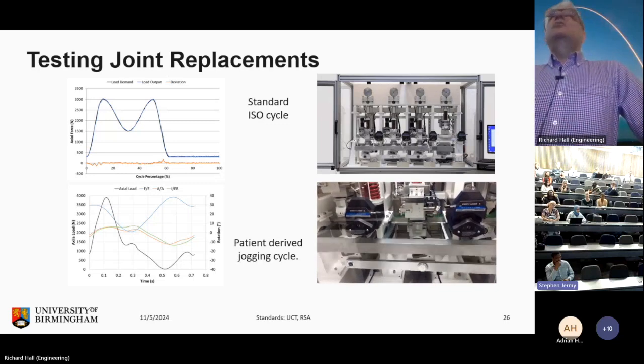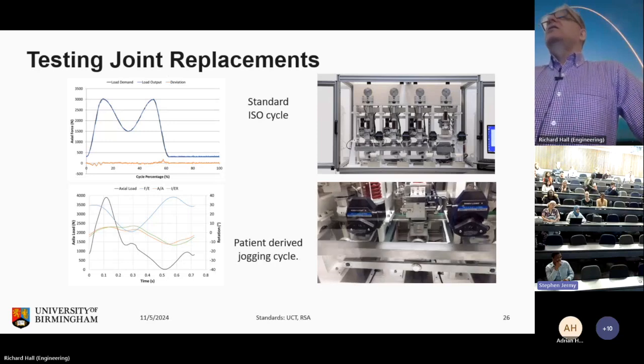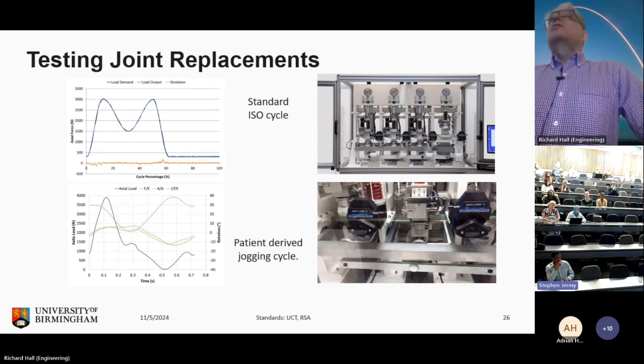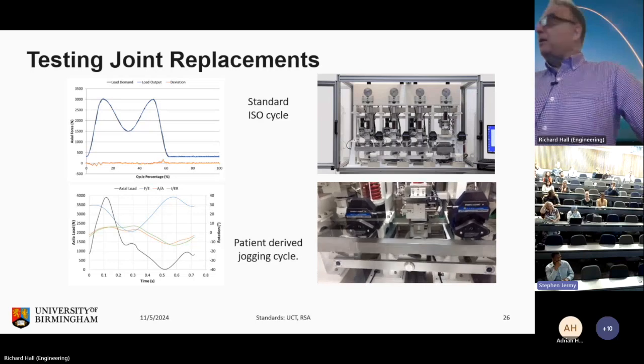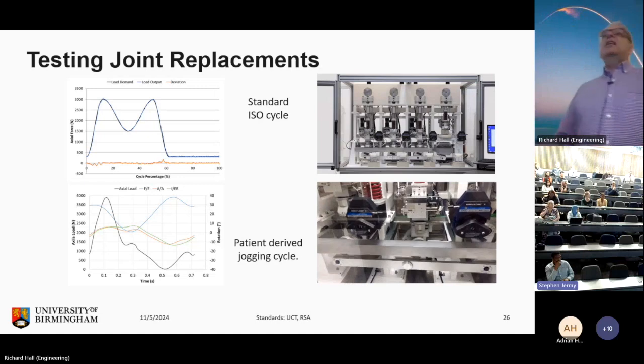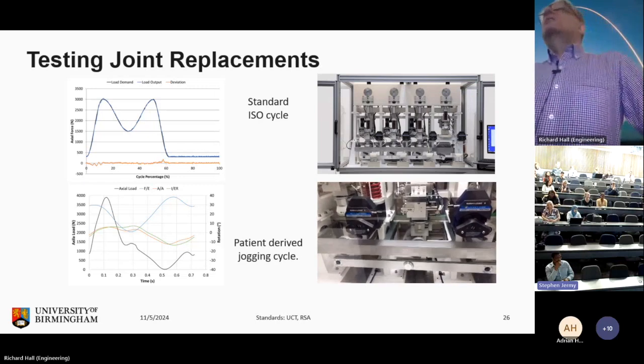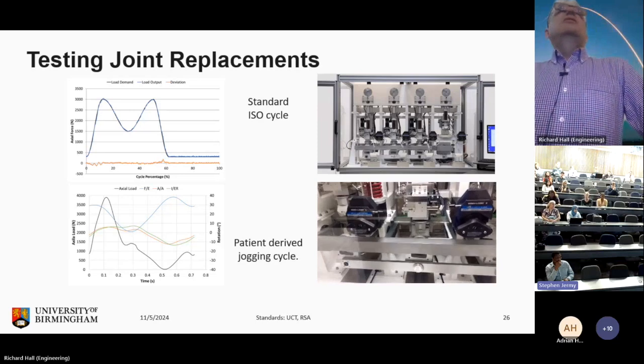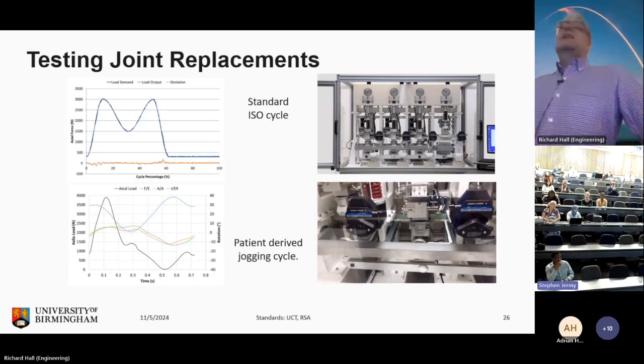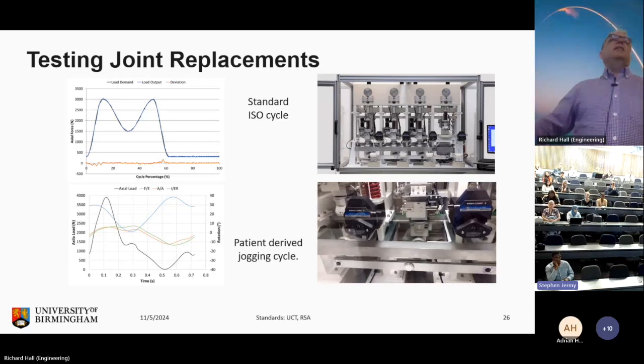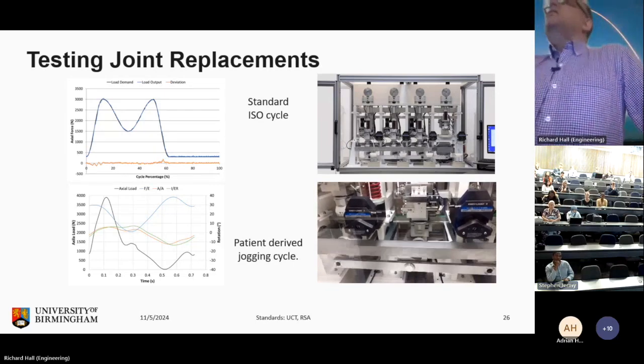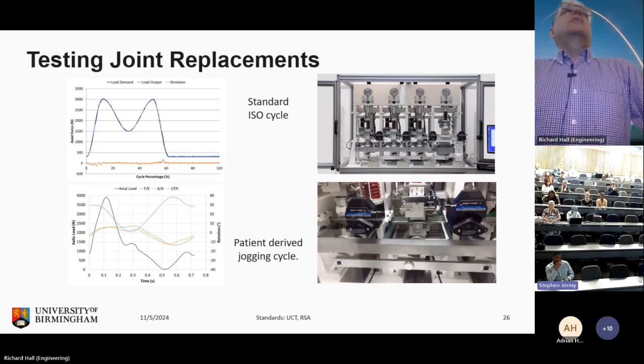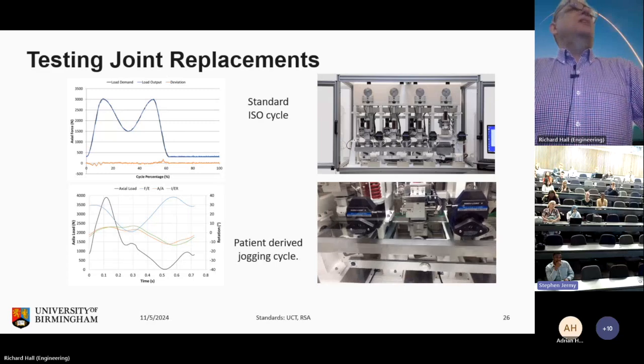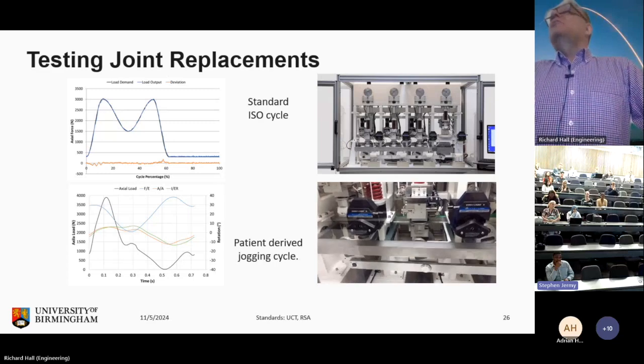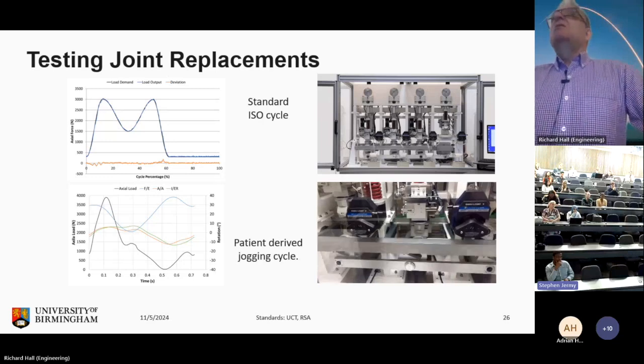So running higher loads, higher rates of change of motion, and higher kinematics. So we have greater extensions of the hip against the acetabulum, as it were. And you get obviously higher wear in those scenarios. In fact, you get 2 to 3 times the wear that you would do in a standard gait cycle. The issue here is most of the simulators in the world, and there's probably not that many, can only run the standard gait cycle. It's only because we're an academic department and we want to go beyond the standard that we can run these adverse scenarios. So we're one of the probably 2 or 3 labs in the world that can run these types of tests.